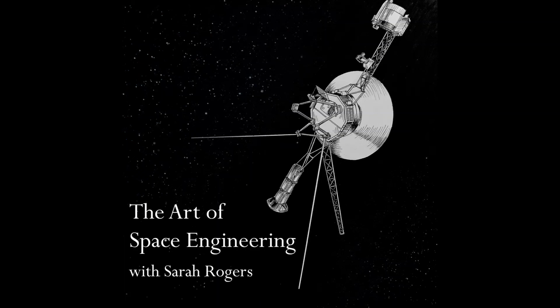And so baking stuff out is another technique that we use to try and take stuff that is covered in volatiles and to boil that stuff away. And the bake out systems that we use often have a vacuum pump attached to them. So as the stuff is baked away, it is then sucked away by this vacuum pump. And you're left with a very clean system when it comes out of the oven. So these are some of the techniques that we choose to use.